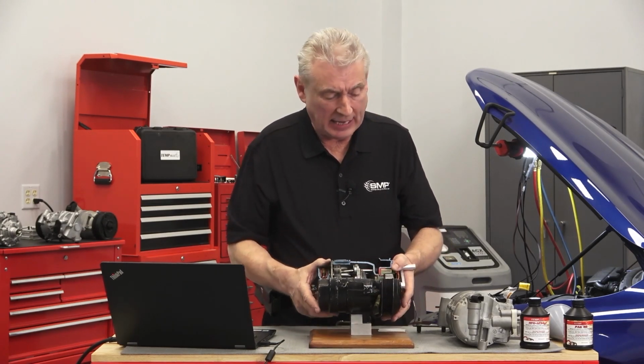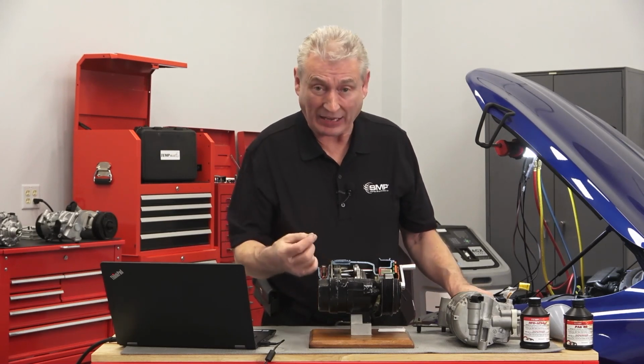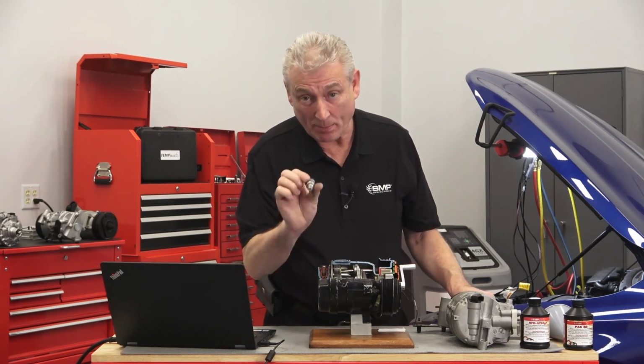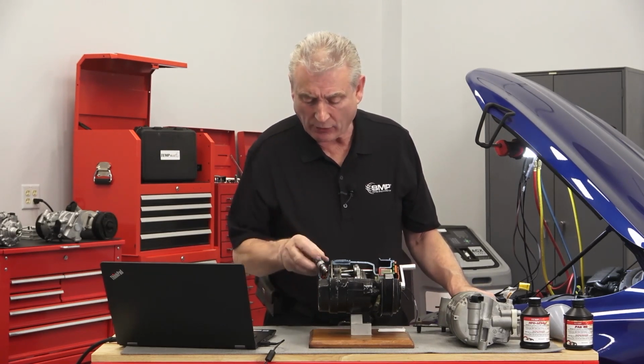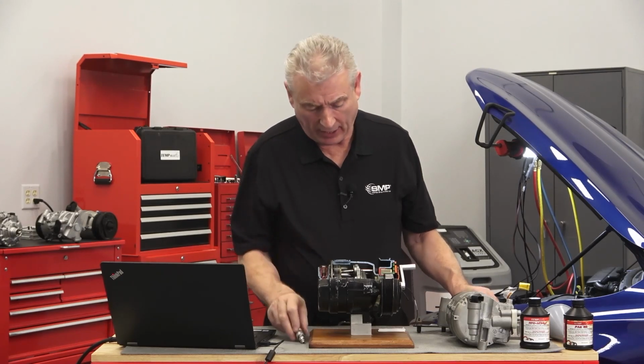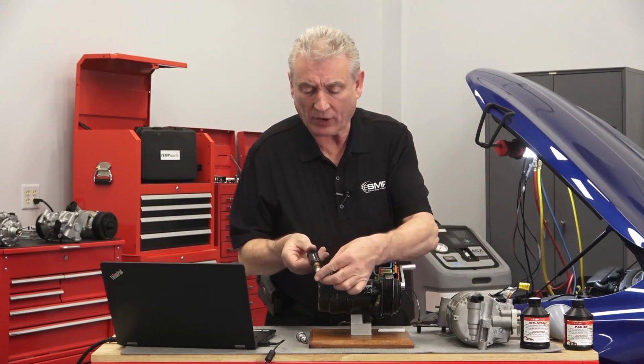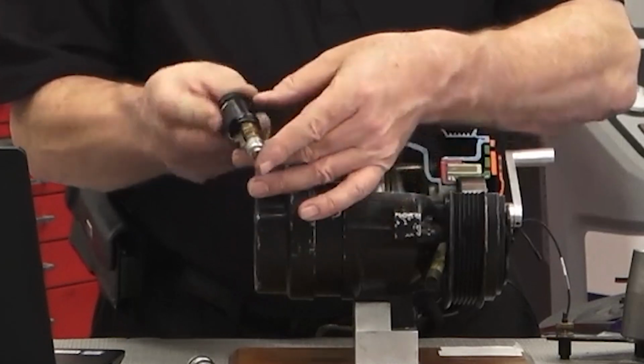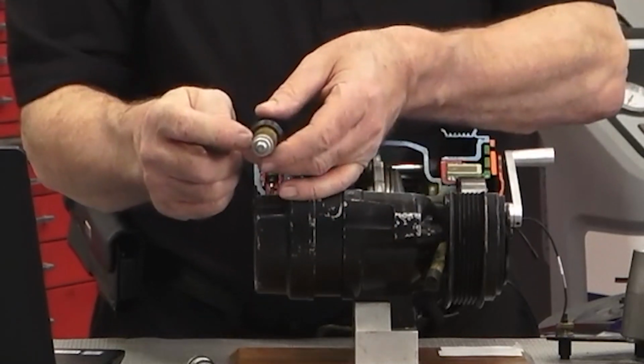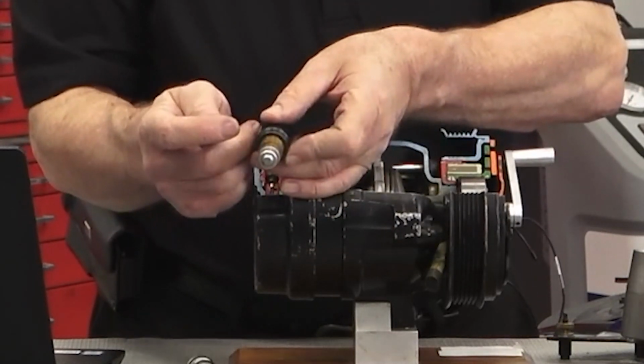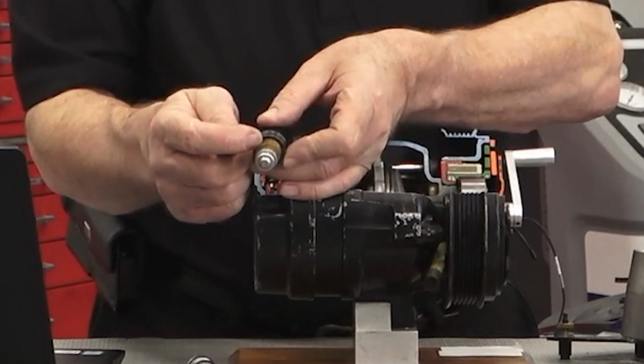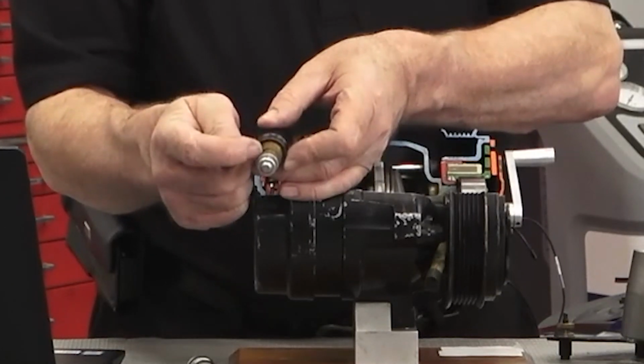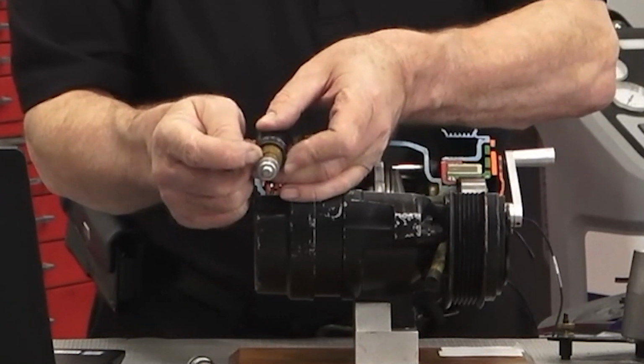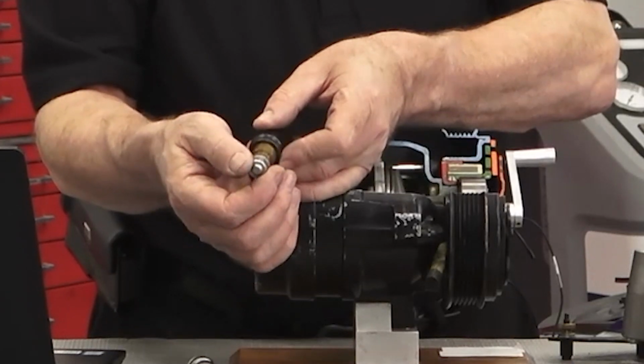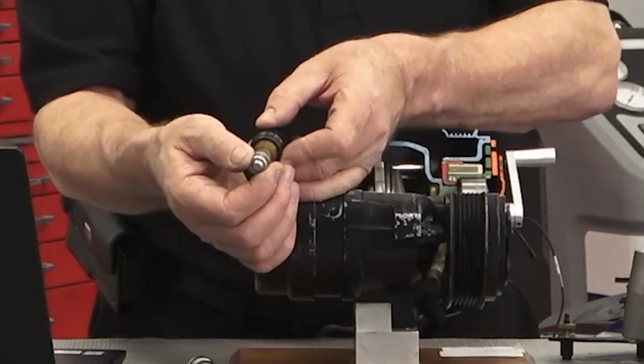So now we need to understand how we get from this simple pneumatic valve to the electronic one. Imagine that I removed this valve, took it out of here, and replaced it with a computer-controlled solenoid. You see this solenoid, I've taken the O-rings off of it, but it still has the same three areas. It's got the area exposed to suction pressure, the area exposed to crankcase pressure, and the narrow tip here is exposed to high side pressure.